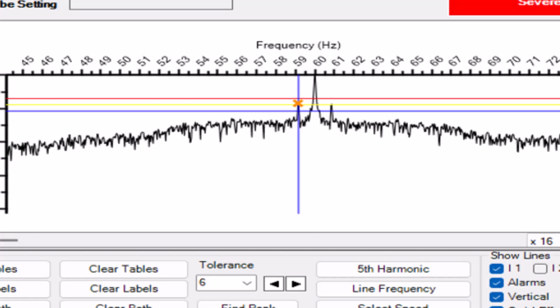In this situation, I really think their decision was driven by opportunity—and opportunity cost—to remove and repair, or replace, or investigate to confirm what we're seeing. It's more of a controlled evolution versus a middle-of-the-night evolution, where gas pumping stops and everybody's got their hair on fire. If you know you're going into an outage and you know you have a potential issue, the best thing to do is have a controlled evolution.